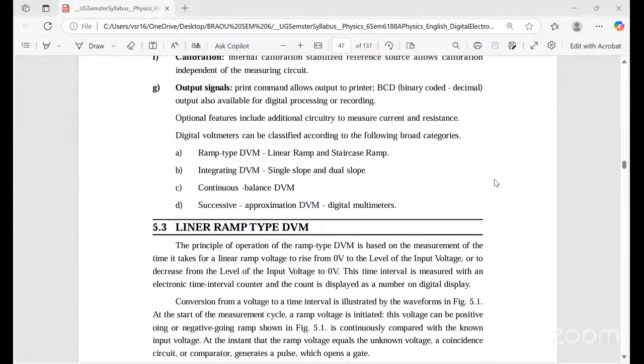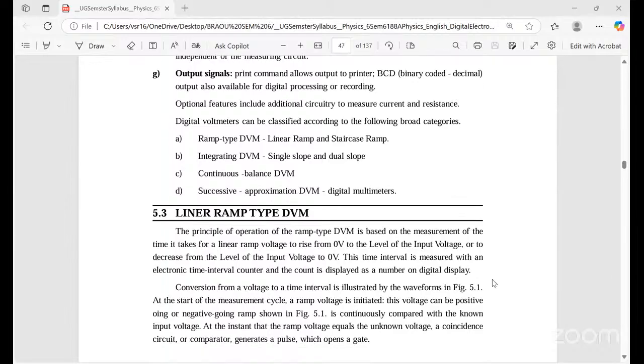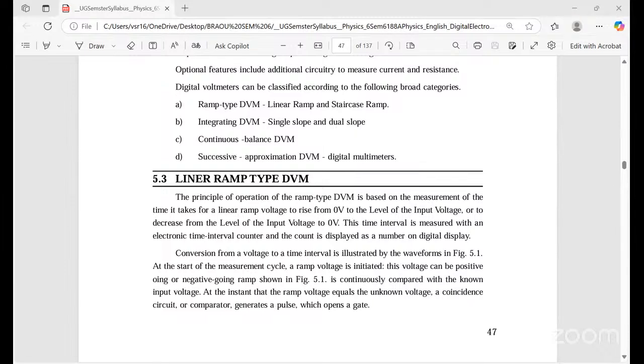Let us discuss the linear ramp type DVM. The principle of operation of the ramp type DVM is based on the measurement of time it takes for a linear ramp voltage to rise to, or decrease from, the level of the input voltage down to 0 volts.